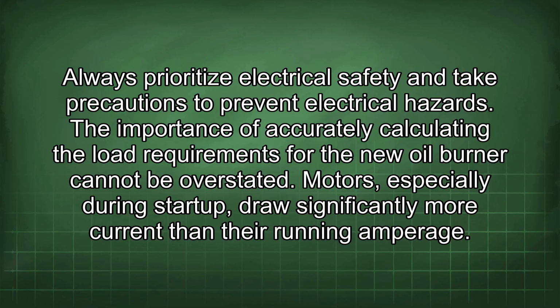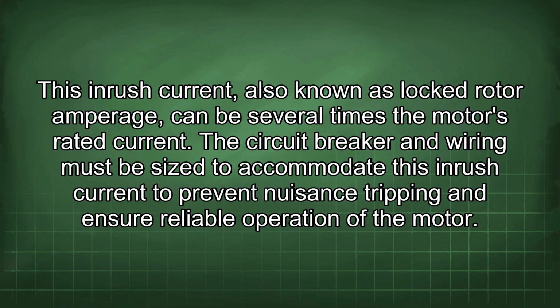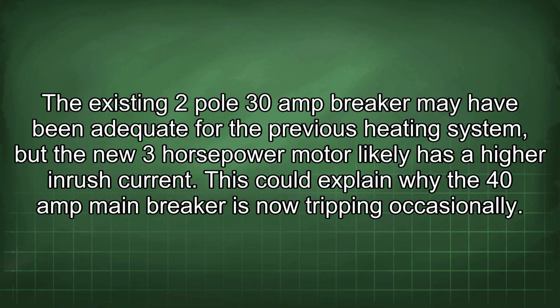The importance of accurately calculating the load requirements for the new oil burner cannot be overstated. Motors, especially during startup, draw significantly more current than their running amperage. This inrush current, also known as locked rotor amperage, can be several times the motor's rated current. The circuit breaker and wiring must be sized to accommodate this inrush current to prevent nuisance tripping and ensure reliable operation of the motor. The existing 2-pole 30 amp breaker may have been adequate for the previous heating system, but the new 3 horsepower motor likely has a higher inrush current. This could explain why the 40 amp main breaker is now tripping occasionally.